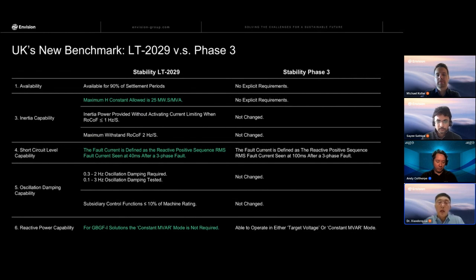The first one is regarding the inertia constant. Now the maximum inertia constant is 25 seconds, but when we reviewed the design, our design is also compliant with it, and the other control functionality was not influenced by this configuration. The second critical one is the fast fault current injection. Previously in Phase 3, the fault current was evaluated at 100 milliseconds after the 3-phase fault, but now it's evaluated 40 milliseconds after the 3-phase fault. We also reviewed our field test result, and it met the requirement even before, without any optimization. I will show you the data later.